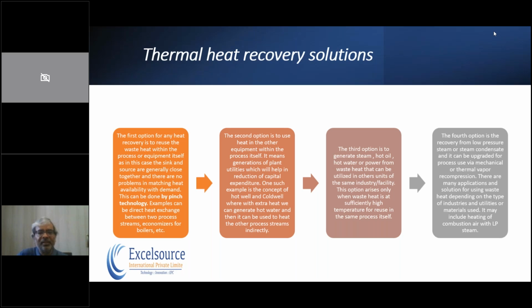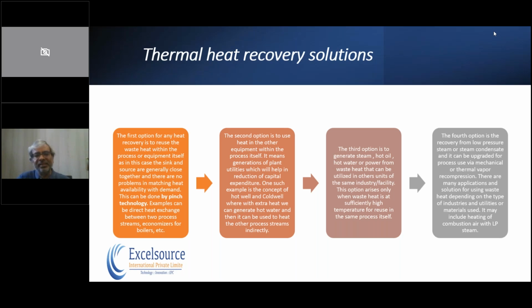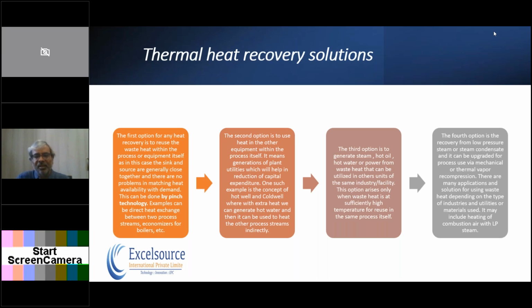The second option is to recover heat that is thrown into the cooling tower, where very low grade heat is available, which cannot be utilized within that particular section. So what can be done? We can recover that heat and make a system, a kind of hot well, where all the heat is recovered and kept. How do we use this hot well heat? We take the heat to the area where low grade heat can be utilized. For example, boiler feed water. We have to heat the boiler feed water from one temperature to another. For a high pressure boiler, deaerator water has to be heated from 30 degrees Celsius to 130 degrees Celsius.